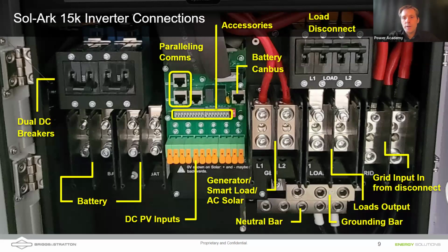On the right side of the screen are 3 different AC connections. So you've got a generator input or maybe a smart load output, or you could bring in AC coupled solar through that generator port. So that's the one on the left. The one in the middle is the loads output. That's rated at 200 amps. And then we've got a grid input on the right side rated at 200 amps. We've got neutral and grounding bars on the bottom there.